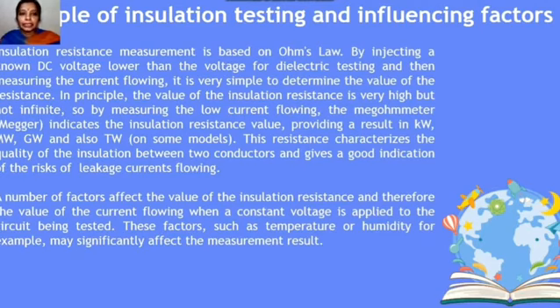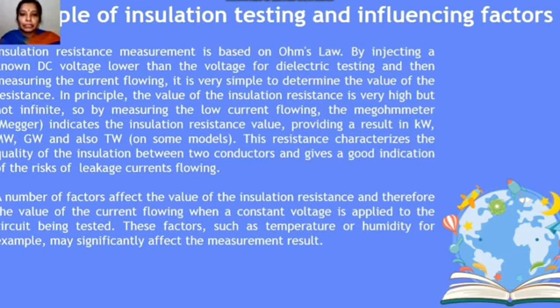Insulation resistance is based on Ohm's law: by injecting a known DC voltage into the dielectric material and measuring the current flow, we find resistance using R = V/I. Since insulation resistance is very high, the current will be very low. A megger is used to indicate insulation resistance in the order of kilohms, megaohms, gigaohms, or teraohms. Factors such as temperature or humidity may significantly affect the measurement result.